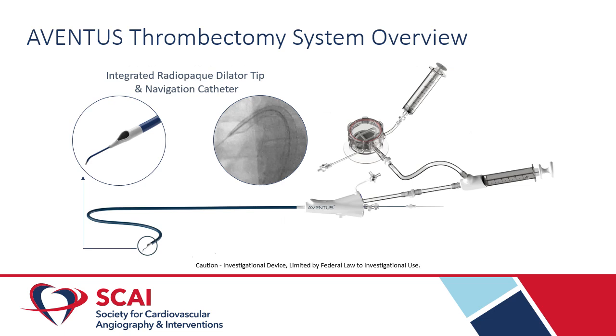The AVENTUS Thrombectomy System is specifically designed to address some of the current unmet needs within the PE space of thrombectomy devices. The integrated navigation catheter and bevel tip obviates the need for multiple wire and dilator exchanges. In addition, an inline filtration system allows us to perform more efficient separation of clot from blood, the latter of which is reinfused back into the patient, minimizing blood loss and shortening procedural time.